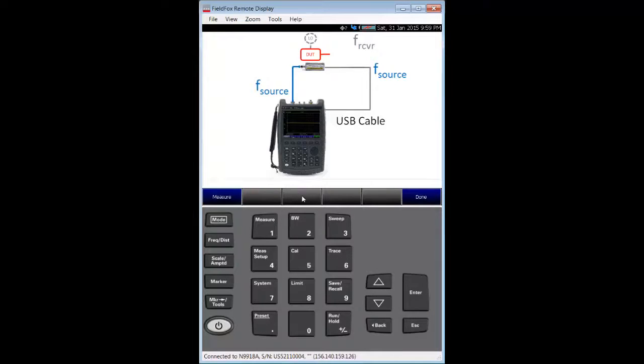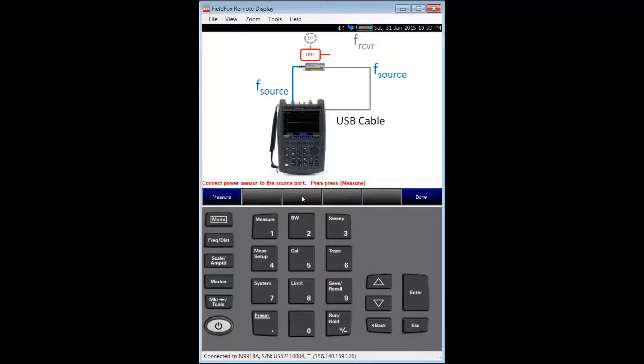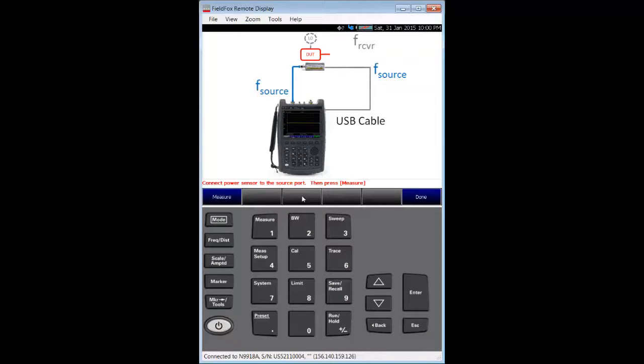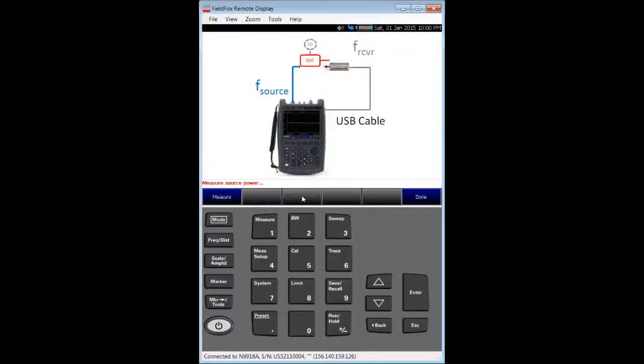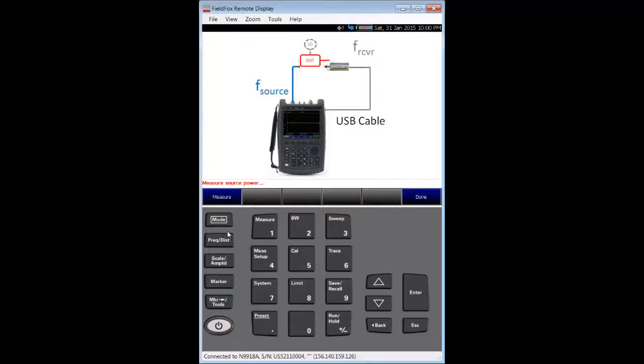And then we store that data trace into memory. The FieldFox screen tells you what to do. I follow the diagram on the screen and mate the power sensor's input to the port one cable connector using a short female to female adapter. I then press the measure soft key.